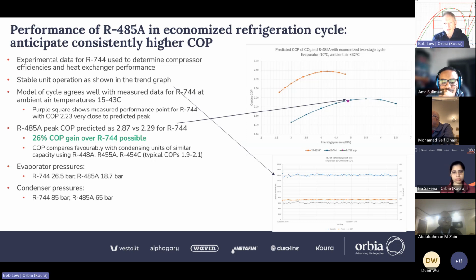The other points to note here, the bottom graph is just a readout of the points from several hours of steady operation. You can see the only takeaway from here is the unit controls itself very, very well and very stably. The rated capacity sits more or less at 16 kilowatts all the way through with very little variation. The power draw stays the same and the COP is almost constant.